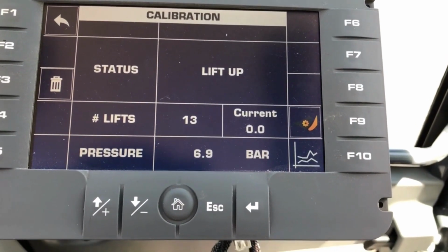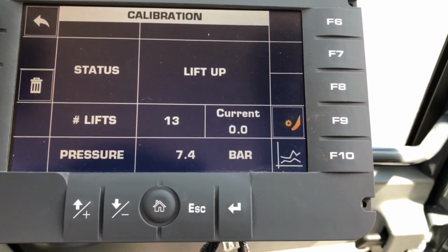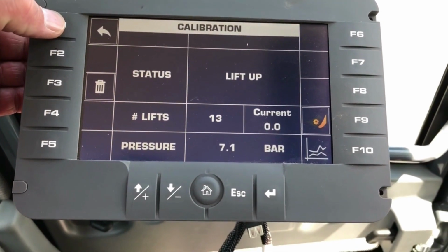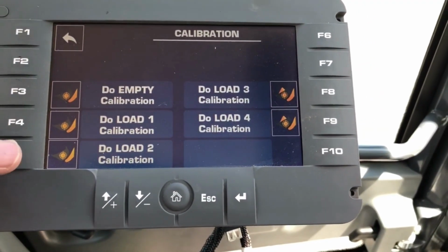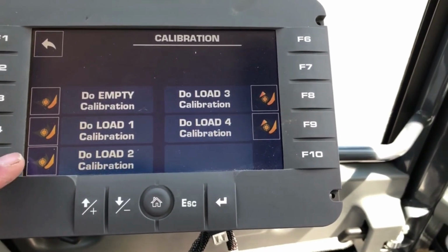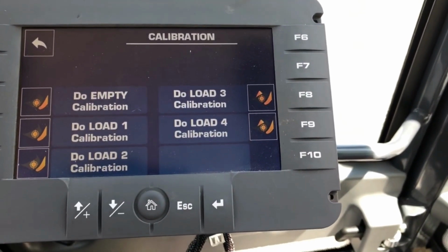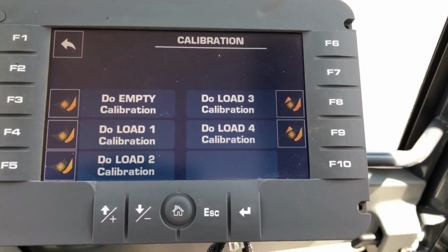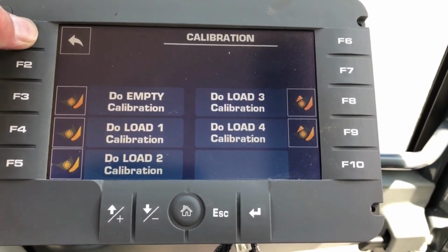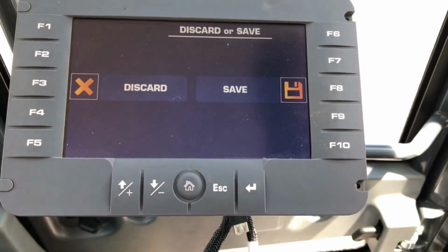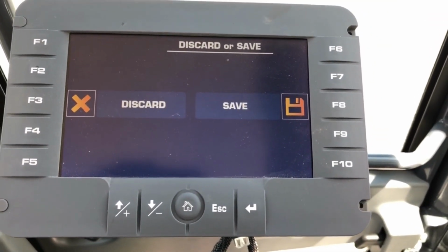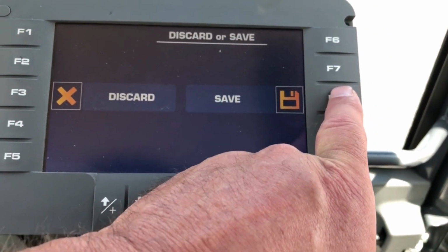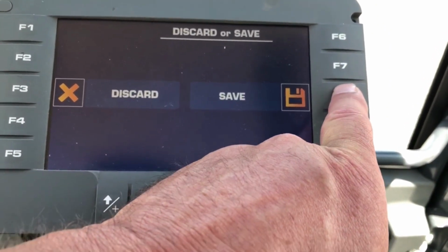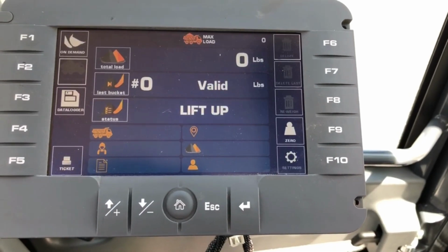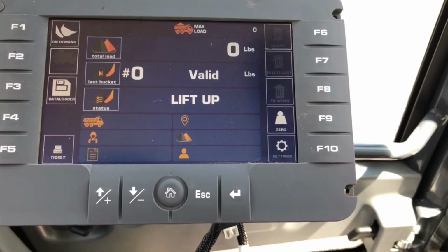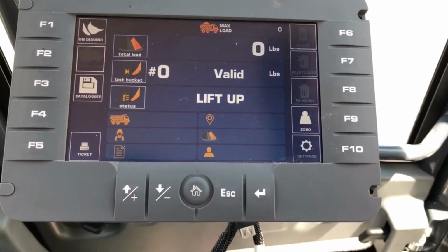And then you continue doing all your lifts, and then hit your F1 to go back, then continue on, do your load 2, your load 3, your load 4. And then once you're done with that, you can go to F1. It's going to ask you if you want to discard or save. We want to save the calibration, so hit F8. Once it's done that, you now have a calibrated scale.